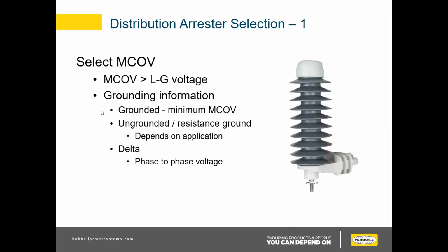Here's a quick example of how we calculate MCOV. It depends on the grounding consideration, like I said, and we have a little snippet from our catalog that helps explain it. For a solid grounded system, that's your minimum MCOV. That makes it super easy. For ungrounded or resistance grounded, it depends on the application, but generally we'll upsize the MCOV to handle any TOV requirements. And then for a delta, which we don't see a ton, we'll pretty much always bump the MCOV up to where it can handle phase-to-phase voltage, just in case the neutral shifts during a fault.